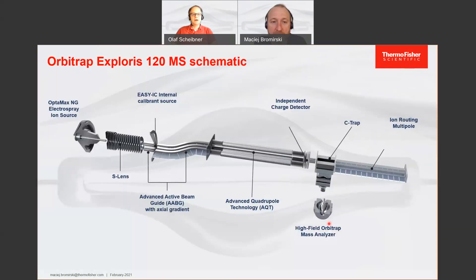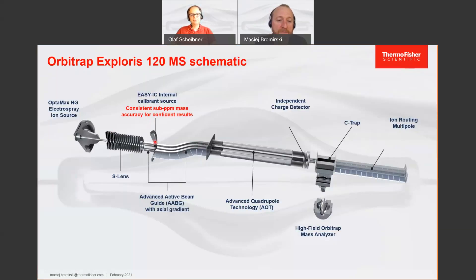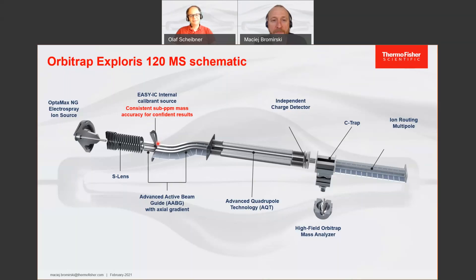To look into the mass accuracy, what is new to the Exploris series instruments is the EASY-IC internal calibration. It sits in the front of the instrument, more or less in the ion path. Technically, it's a little EI source that produces fluoranthene ions, which works very well on both polarities. With this device, we can introduce a well-known species for internal calibration — we know exactly what we calibrate on. On the other hand, we can control the signal intensity, so we don't put too many ions into the system, which would affect the sensitivity of the system with too many calibrant ions in the scans.